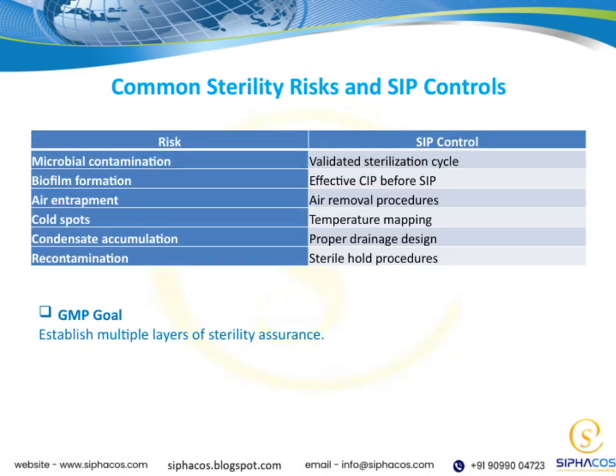Our goal here is to build multiple layers of sterility assurance, a safety net that catches risks before they become problems. We're looking at common sterility risks, like microbial contamination, and matching each one with a control measure. For example, validated sterilization cycles tackle microbes, while effective cleaning before sterilization stops biofilms. We also remove air pockets, monitor temperatures to avoid cold spots, design proper drainage to prevent condensate, and use sterile hold procedures to avoid recontamination. It's a comprehensive approach, covering every angle.